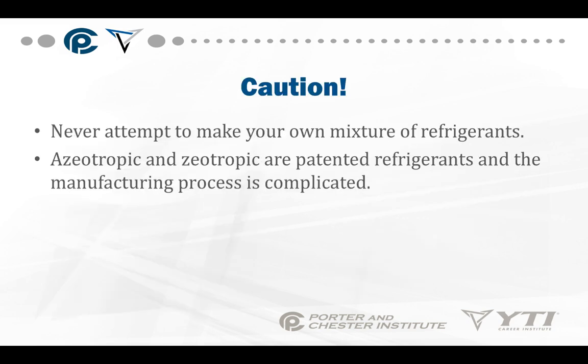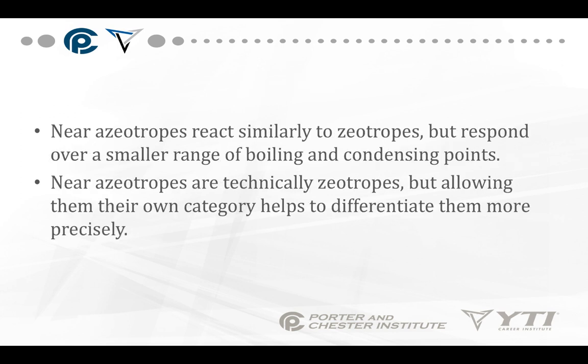Never attempt to make your own mix of refrigerants. Azeotropic and zeotropic blends are patented refrigerants and the manufacturing process is complicated — you cannot just mix these things together. Do not ever mix refrigerants. Near-azeotropes react similar to zeotropes but respond over a smaller range of boiling and condensing points. Near-azeotropes are technically zeotropes, but allowing them their own category helps to differentiate them more precisely.